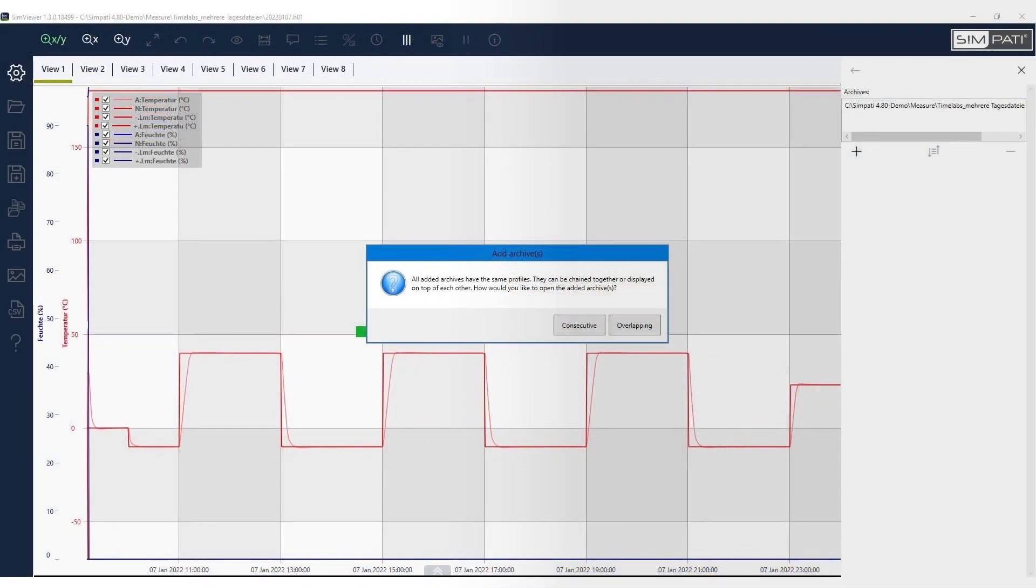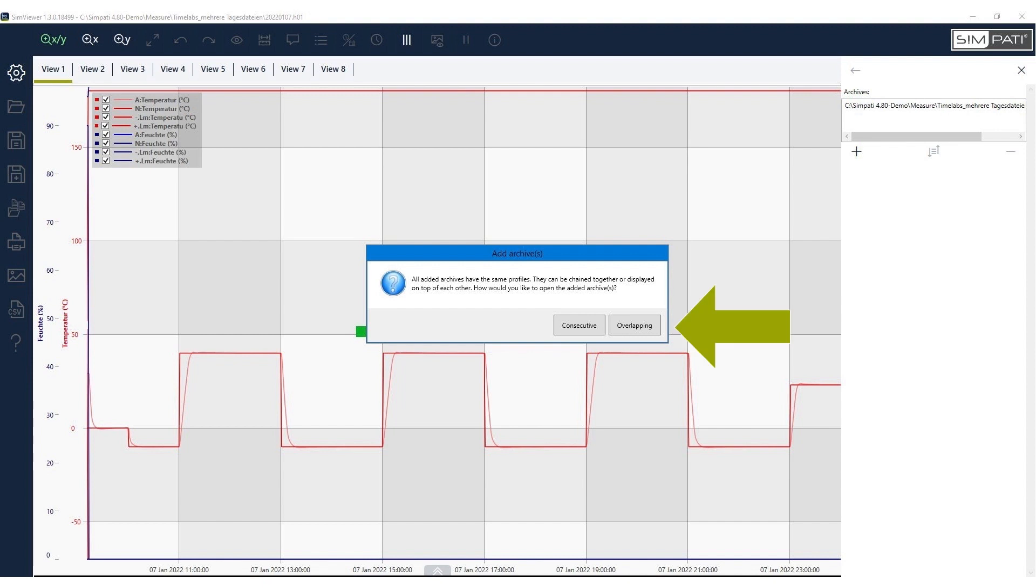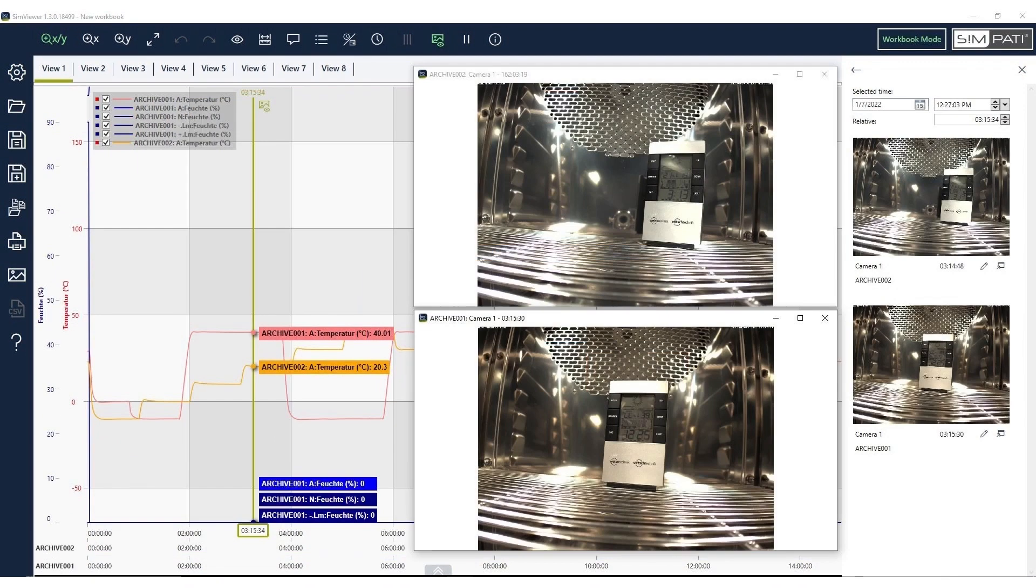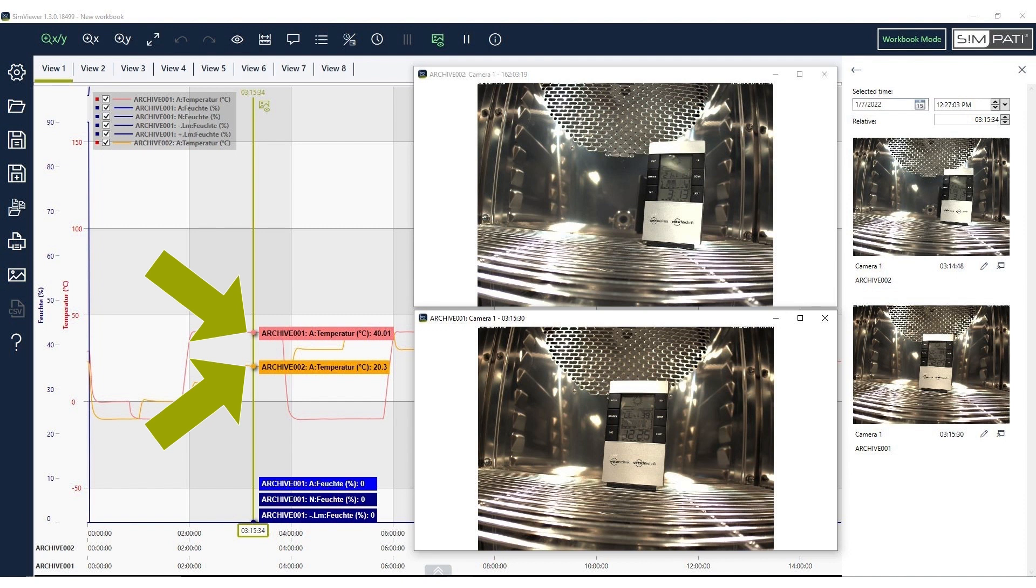As of Update 4.80 Patch 1, evaluations and image material from different test runs and chambers can be overlapped and compared. On a push of a button, you now overlap your reference graphs with the graph of your current test runs. This allows you to quickly and easily compare different archives for optimization of your test runs.